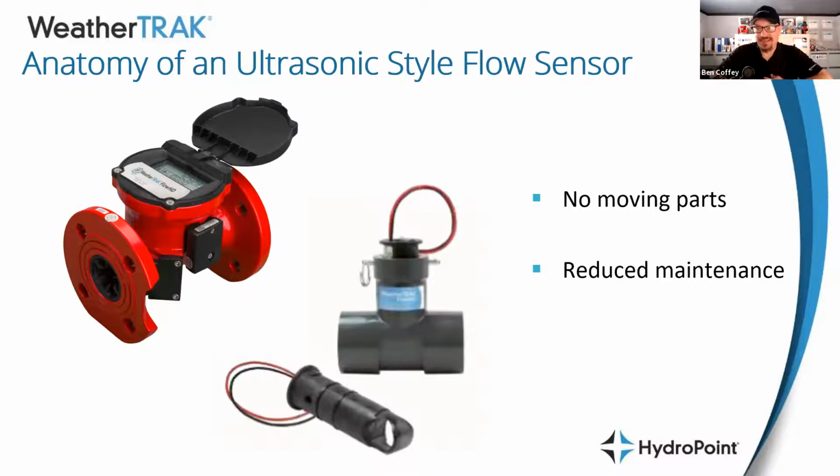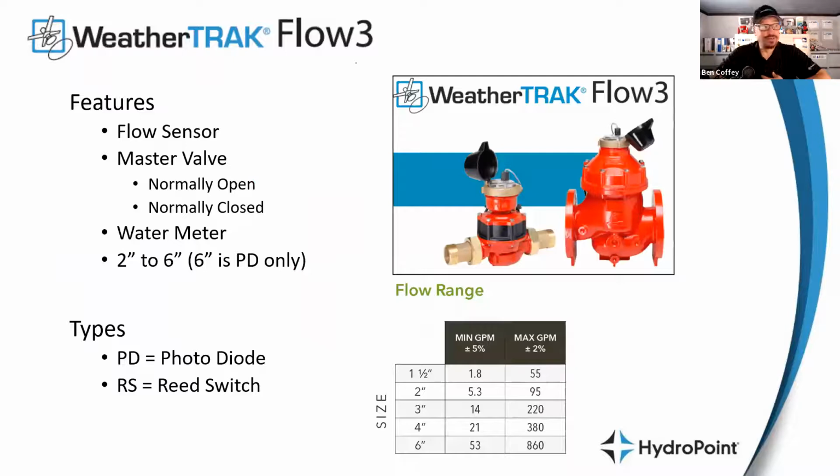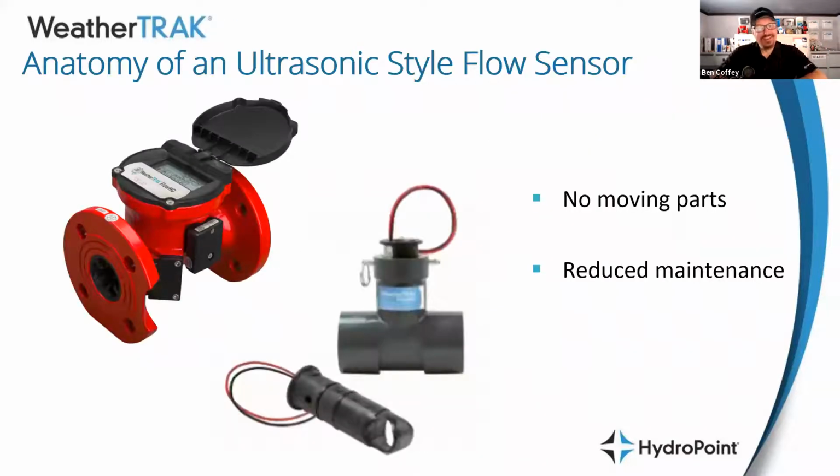On a 2-inch line, we can measure down to a gallon a minute, which is not the case with the Flow3, right? We're accurate down to 6 gallons a minute with the Flow3 at that size, and we're down below a gallon a minute. So the new wave, the cool nerdy new thing, is ultrasonic flow sensors. I actually saw a test this week that the ultrasonic manufacturer measured to 6 gallons a minute on a 12-inch line. So it is a ridiculous advantage.